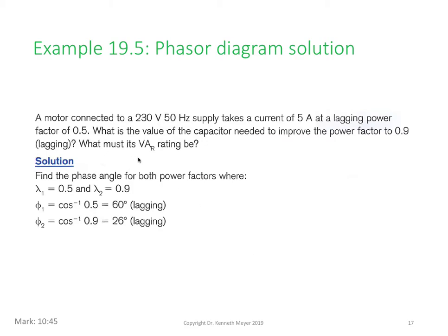So here's our phasor diagram solution. Our motor was connected to a 230 volt, 50 hertz supply, took 5 amps. Power factor was at 0.5. We wanted to improve it to 0.9. So how much VAR rating would we need to add in?